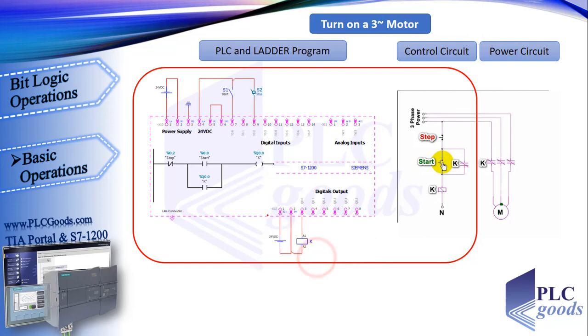Although the second and third lines are different, their performance is similar, because of the different push buttons used in PLC wiring. Now let's see this project which we've done before. Because all used push buttons were normally open, the ladder program is similar to the industrial control circuit. According to the previous slide, if a normally close push button is used in PLC wiring instead of a normally open one, we must change its related contacts to avoid changing the PLC performance.